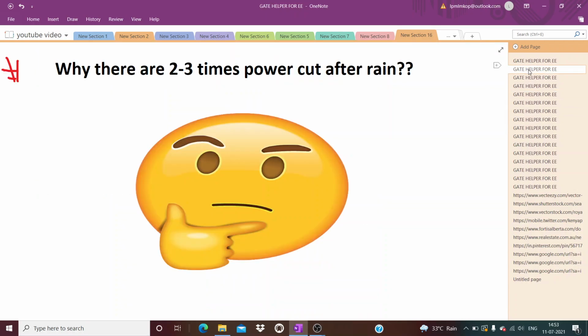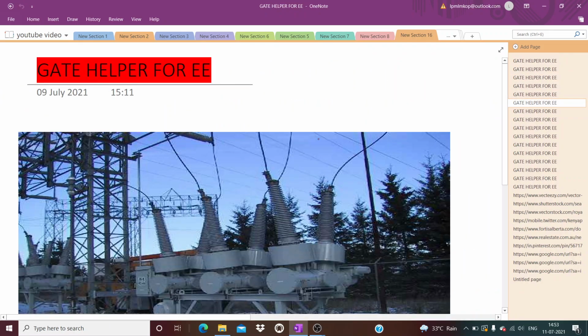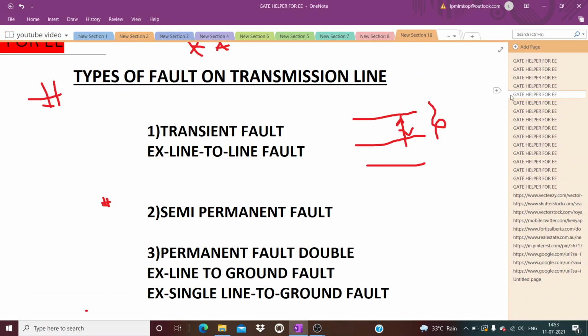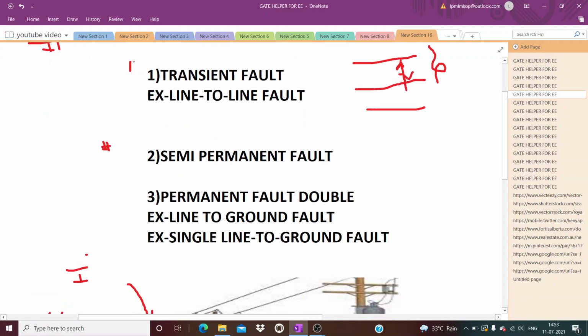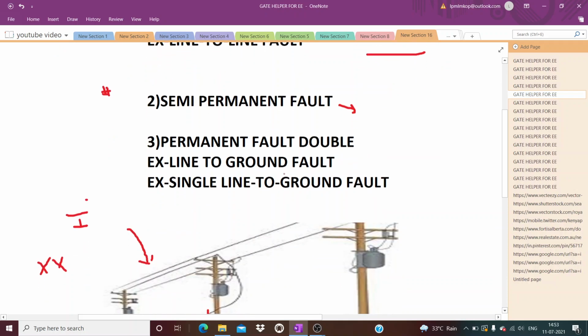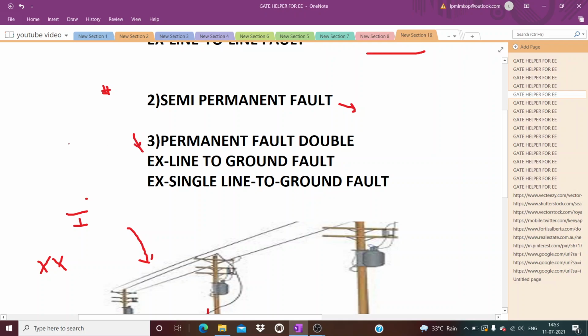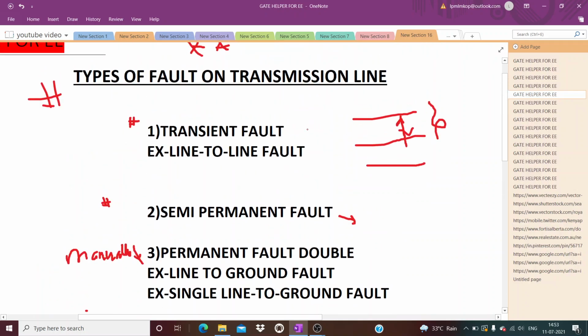So the reason for this 2 to 3 times power off is that we have to check what type of fault our transmission system has. If it's a transient fault, it can be recovered within a few seconds. A semi-permanent fault will take some time to clear. Then we have a permanent fault, which needs to be manually corrected. So we need to know which type of fault this is.